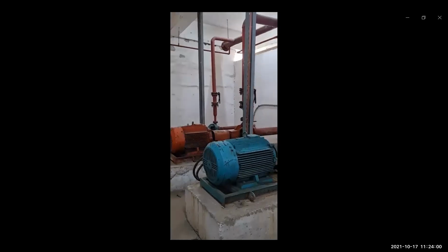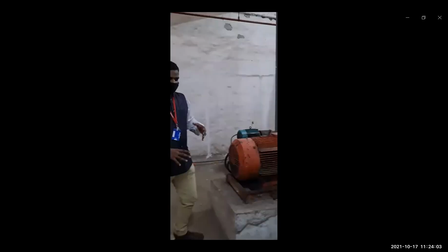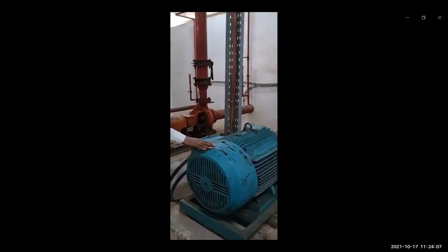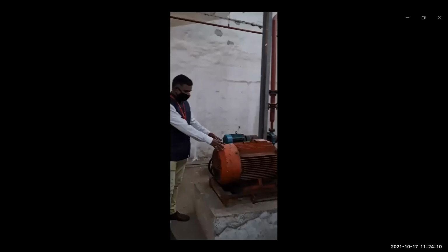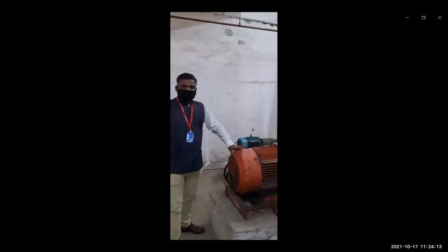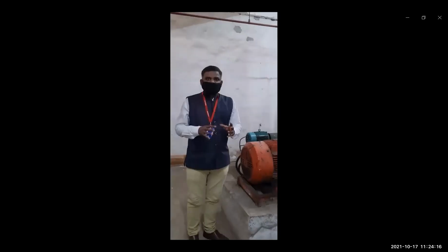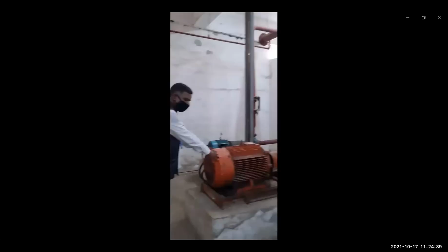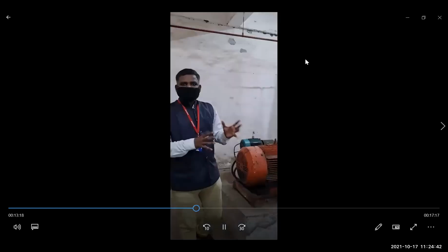I'll tell you the types of pumps installed here: this is the sprinkler main pump and this is the hydrant main pump. In the periphery area we also have many hydrant points, which are fully charged. Once there is a fire call or someone uses water through those hydrant points, the pressure decreases, and this pump automatically starts operating to pump water to those hydrant points. This is the main hydrant point.